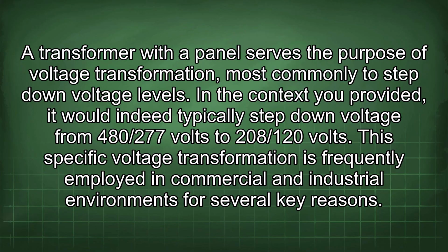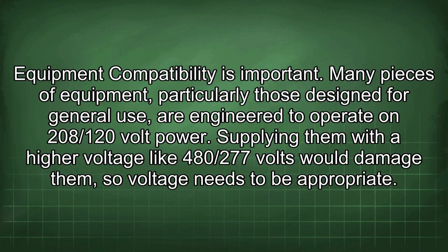A transformer with a panel serves the purpose of voltage transformation, most commonly to step down voltage levels. In the context you provided, it would indeed typically step down voltage from 480/277 volts to 208/120 volts. This specific voltage transformation is frequently employed in commercial and industrial environments for several key reasons. Equipment compatibility is important. Many pieces of equipment, particularly those designed for general use, are engineered to operate on 208/120 volt power. Supplying them with a higher voltage like 480/277 volts would damage them, so voltage needs to be appropriate.